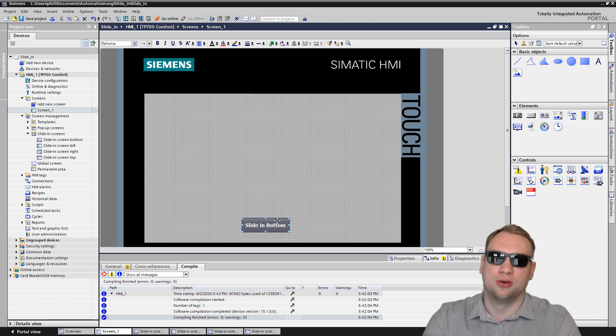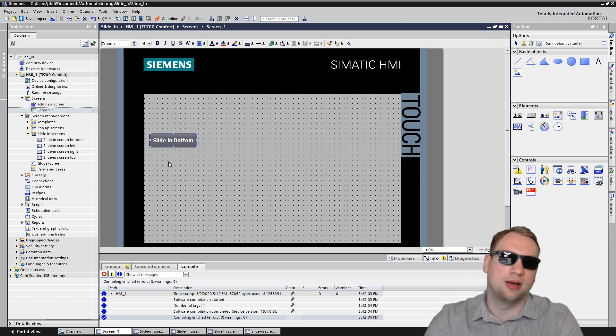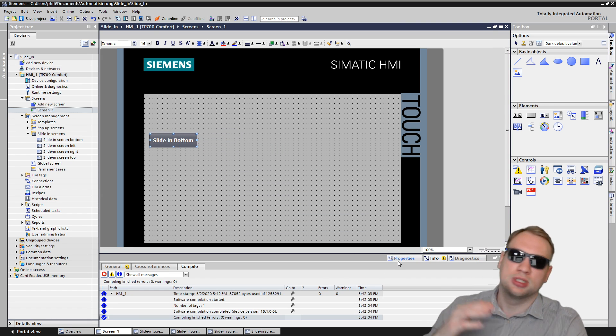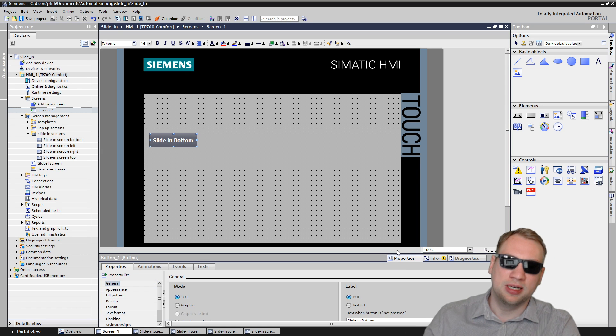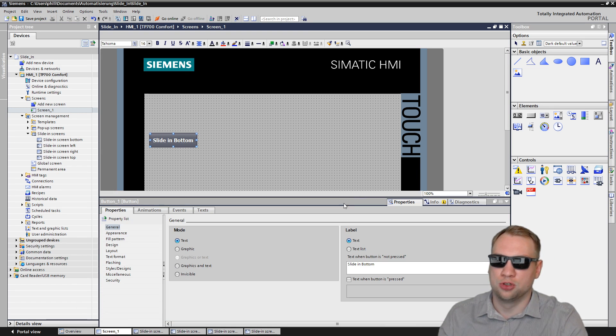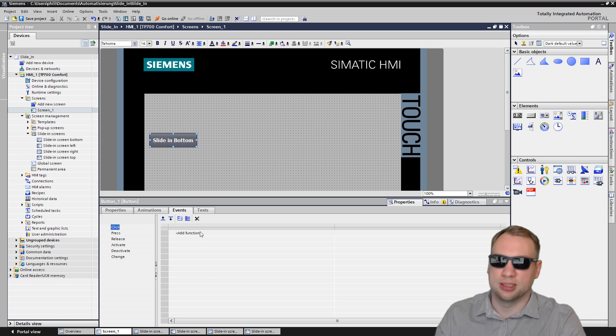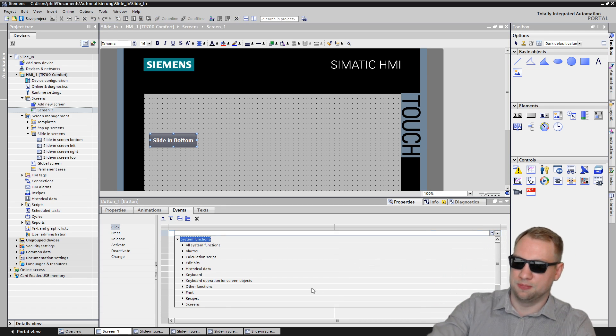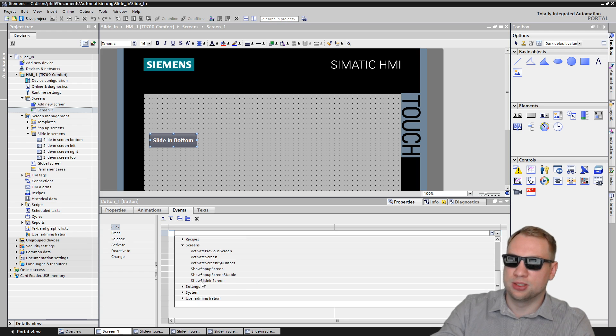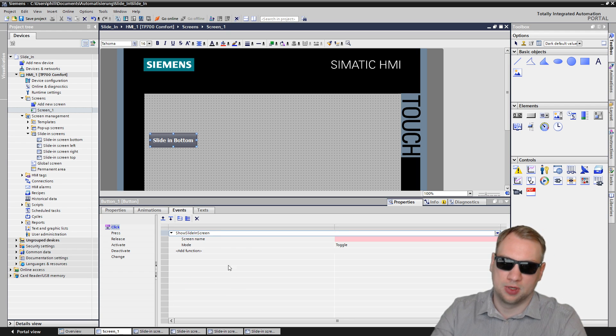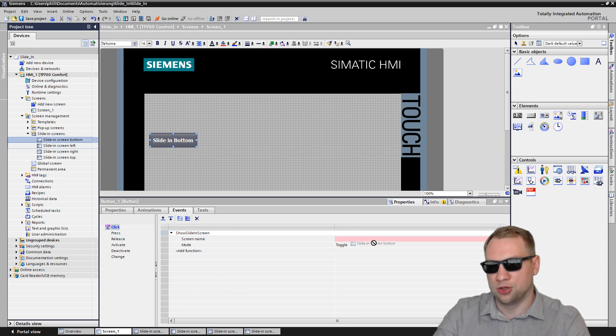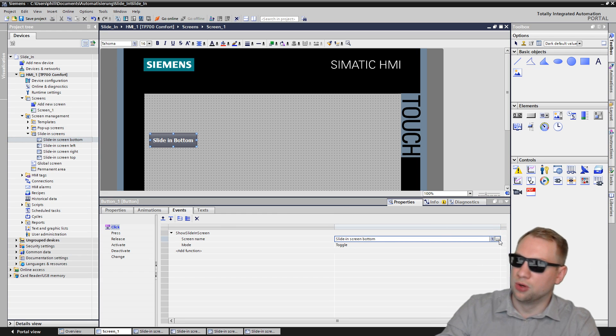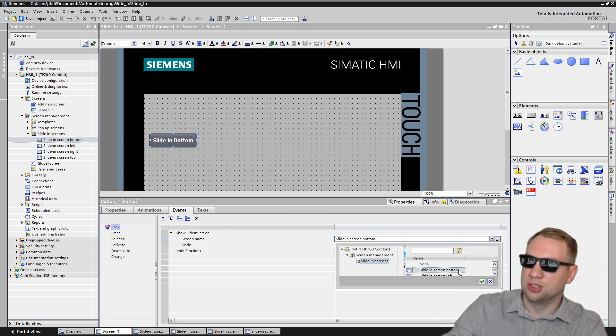That is slide-in screen bottom. And if I press this button, the slide-in screen here on the bottom should show up. We just have to assign the event to it. So I'll go to properties, when on the push button, events, when it is clicked. And then we go to screens. And there is show slide-in screen. Then we need the screen name. I can just drag and drop from the list, or we could have just gone here and just selected it.